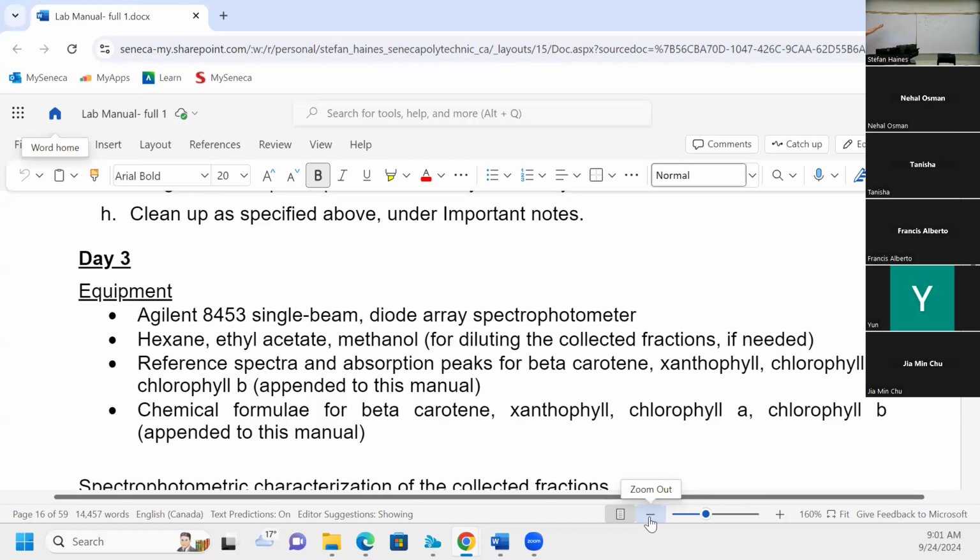You could do a derivative of the formula if you got the curve, but we're not going to do that. We usually just dilute a little bit, bring it down, and then you'll get the sample. So in instrumental, a lot of my students are noticing that the fluorescence spectrometer is maxing out at 99999. And they're like, oh, it's very consistent. I'm like, you're maxing it out. Right? So you have to dilute your sample a little bit.